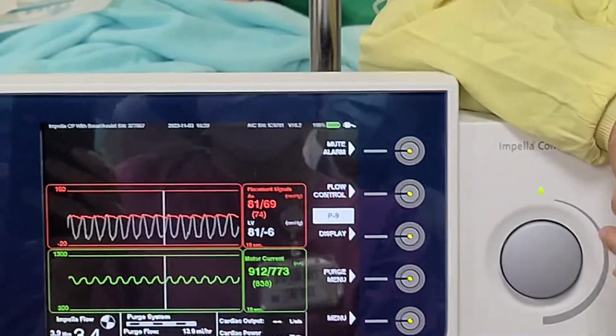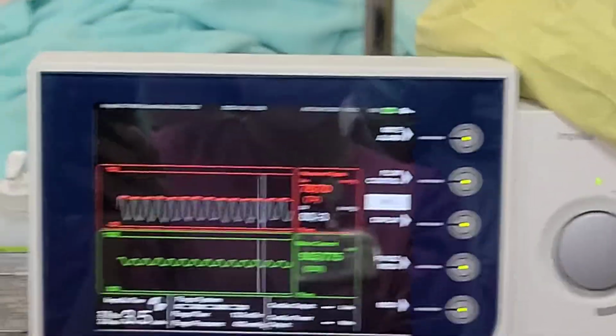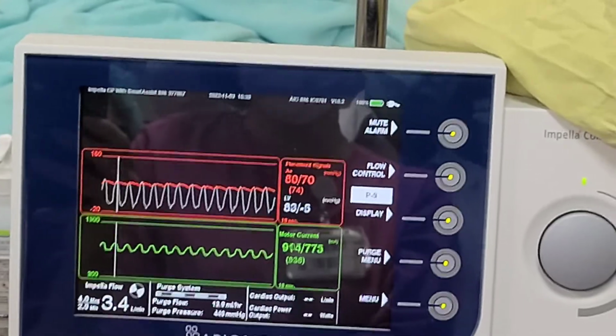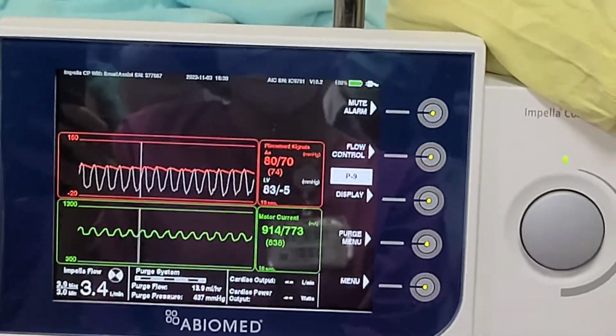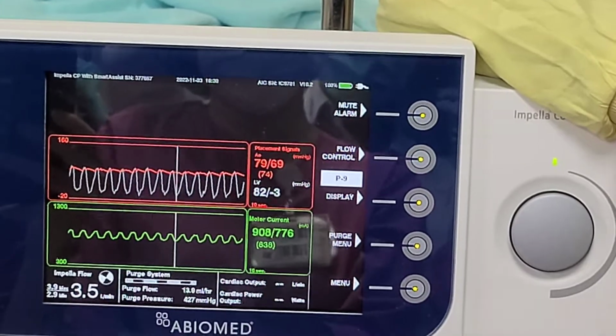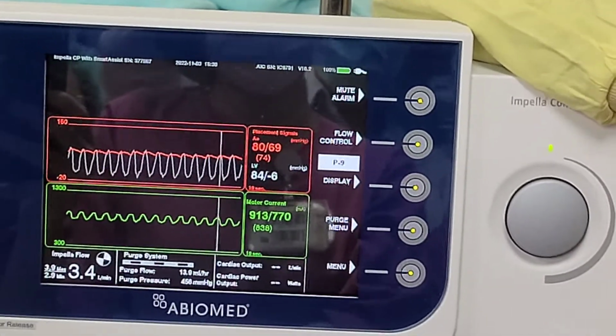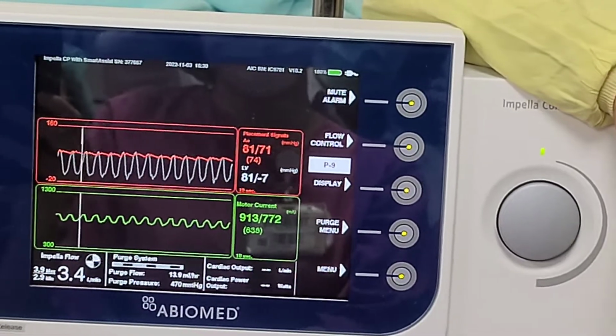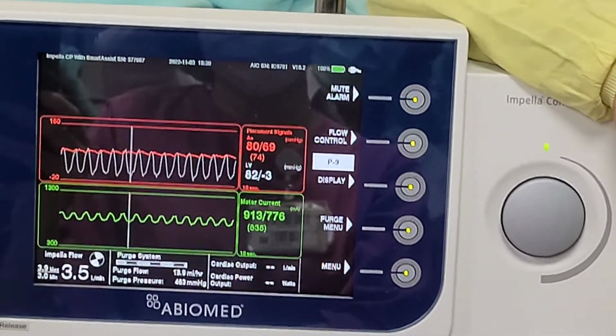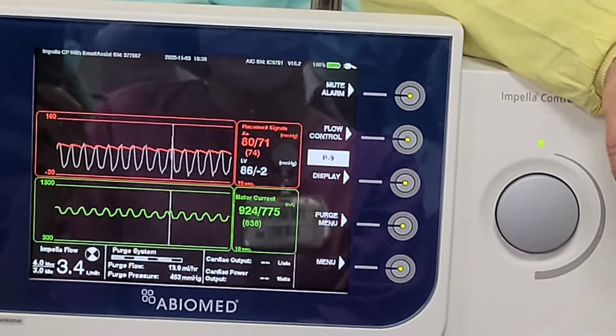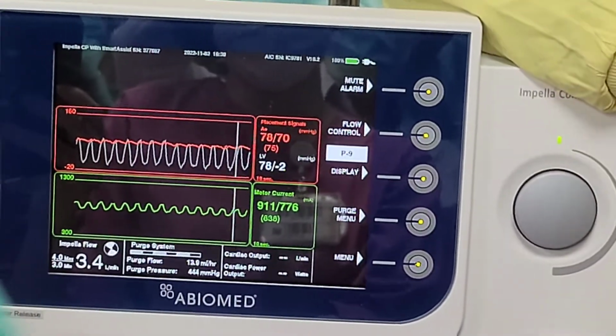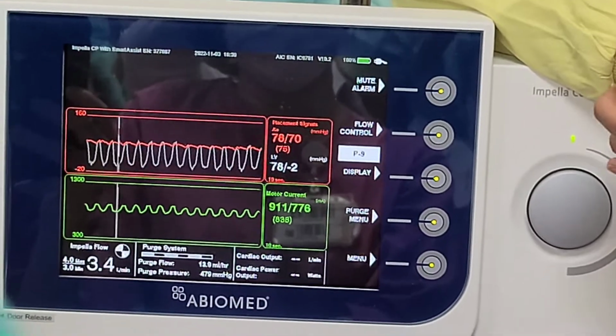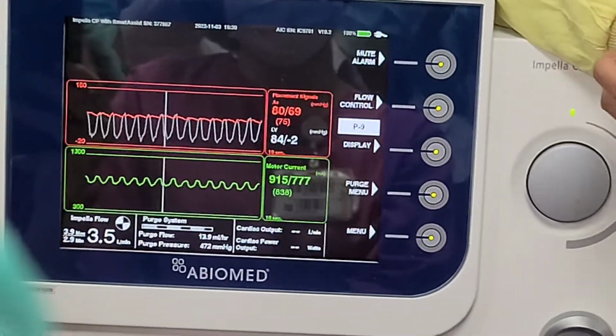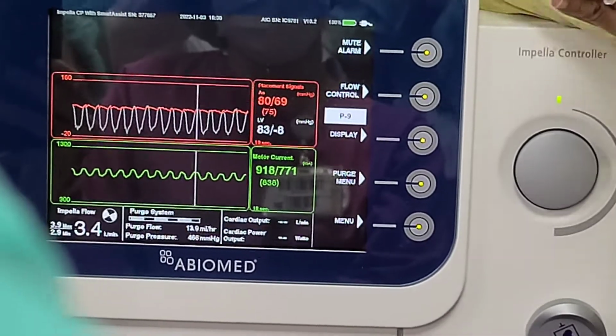Right. So your question about troubleshooting. Common alarms that you could get. One is the suction alarm. The suction alarm is a common troubleshooting alarm. Why will you get suction? There are 3 reasons and only 3 reasons. One, the Impella is preload dependent. So if there's not enough volume, you will get suction. Just imagine drinking bubble tea in a plastic cup: when there's no more tea and you suck, the wall will collapse. Same thing. So, not enough preload.